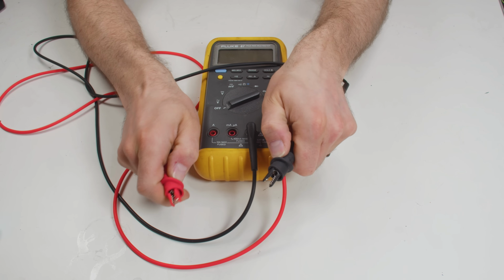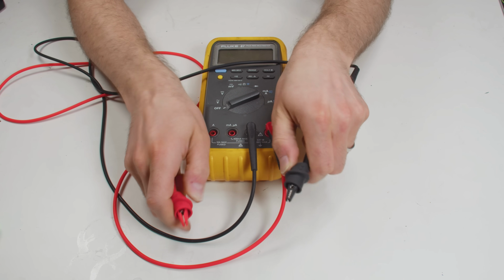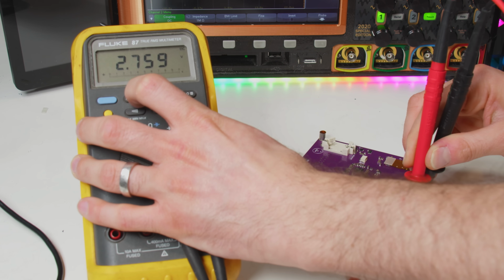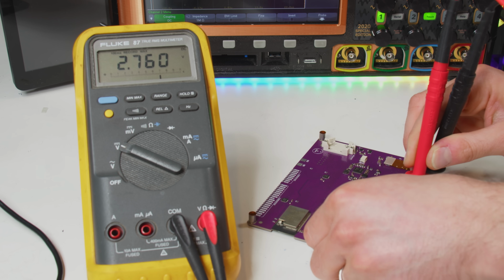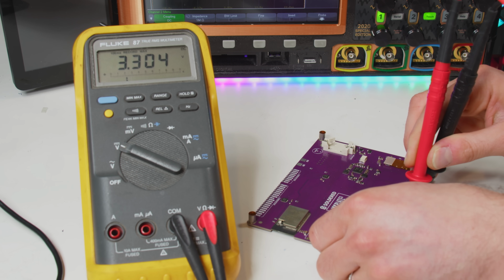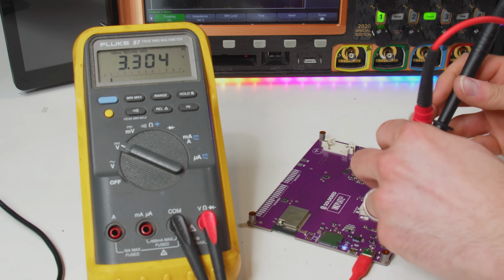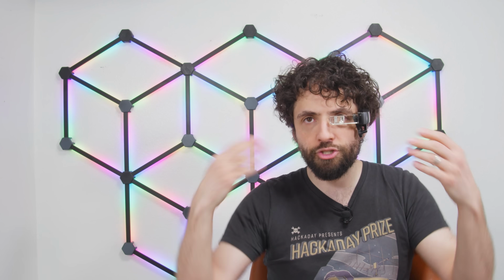Speaking of high voltages, that is dangerous. Attach the meter with alligator clips before you turn on the power, and never ever work on high voltage by yourself. Most meters just show the last reading, but some have a few useful bonus modes. If you're looking for a sudden drop or a spike, switch on minimum or maximum mode and listen for the beep. These are also useful for capturing a single reading when you have to keep your eyes on, say, the extremely dangerous 120 volts you're probing for some reason.